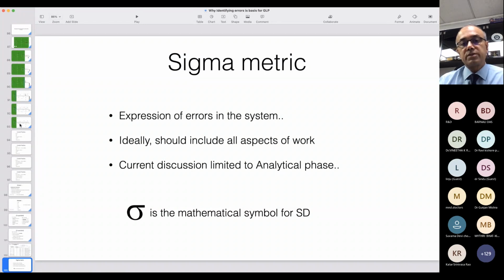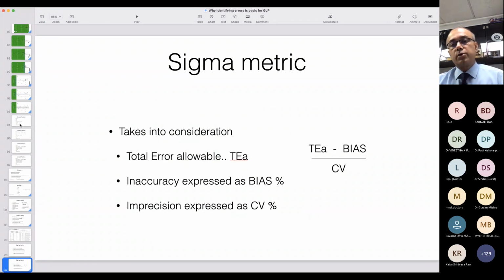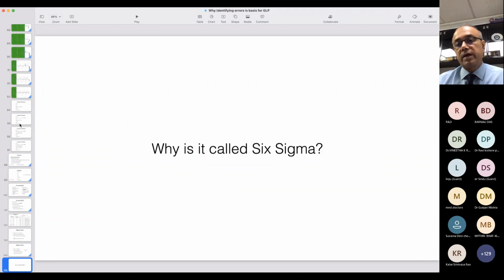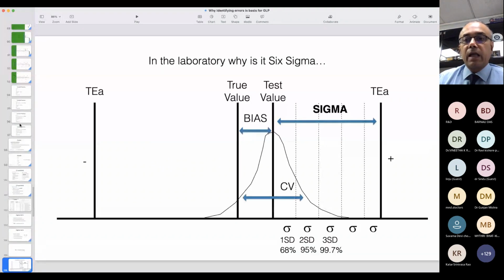Ideally, it should include all aspects of work. And currently, the discussion is limited to the analytical phase. So I told you about total error allowable, which comes from the Milan hierarchy. The bias and the CV come from our own data. Now, with this, can we measure our sigma? Why it is called Six Sigma was a paradox for me, because we all talked about being well within 2 standard deviation, but here we call it a Six Sigma.